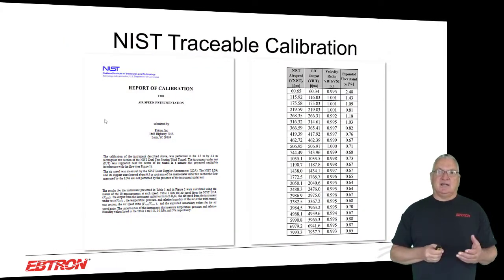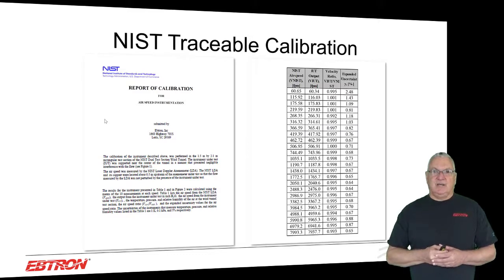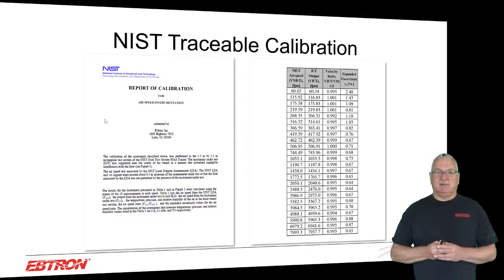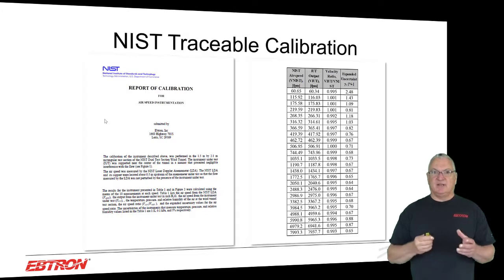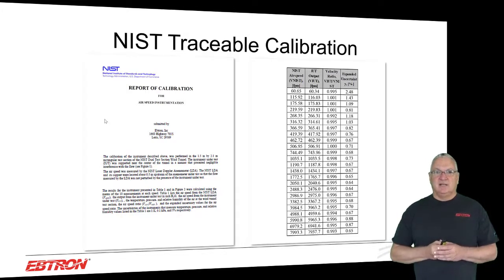When it comes down to the calibration process, we do not do the AMCA process. I'm not a big believer in it. I can tell you why if you want to give me a call. We basically believe in NIST, which is the National Institute of Standards and Technology. It's very independent. We send our calibration standard to NIST with an individual that accompanies it. They provide us with this report on calibration.